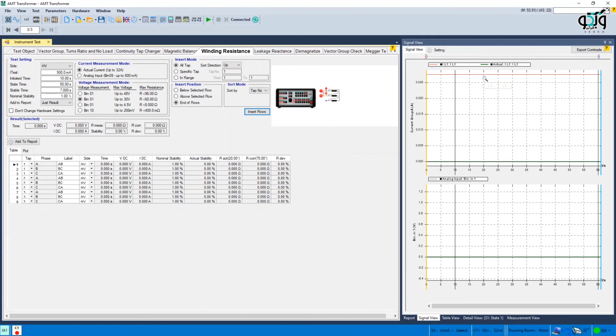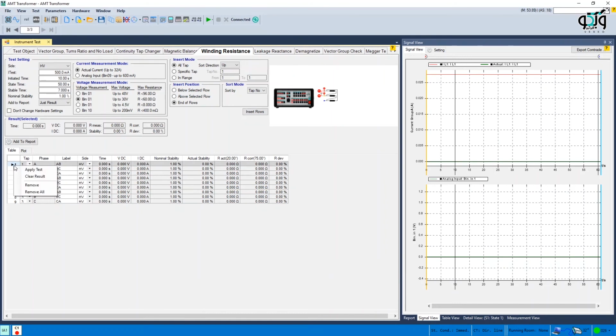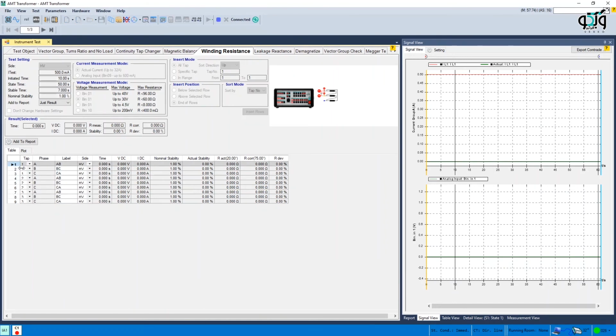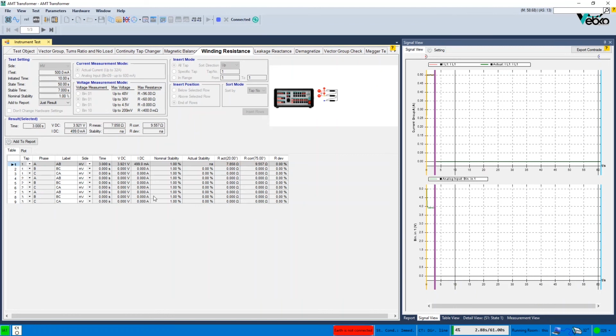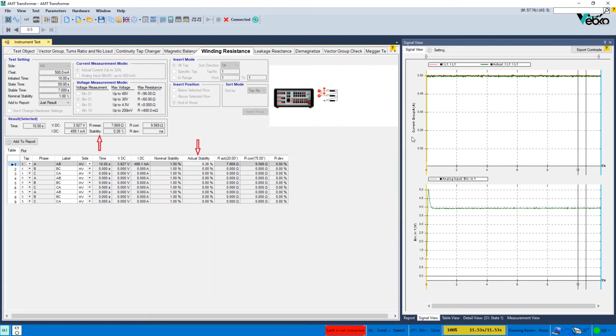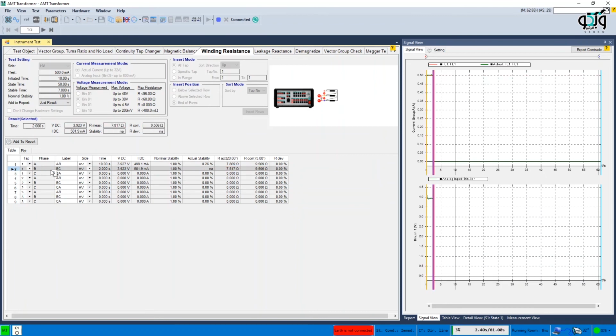The wiring is adjusted in accordance with the guide picture. Then the first row is selected and the test runs by pressing Apply Test. By running the test, the changes of the measured voltage as well as the injected current can be viewed. You can see that by changing the voltage and the current, the value of stability changes, and the test goes on until these changes reach below 1%. After the test is finished, the actual voltage and current, stability, and the measured and corrected resistance are inserted in the test object. To continue the test, two other rows are selected and the test is applied.